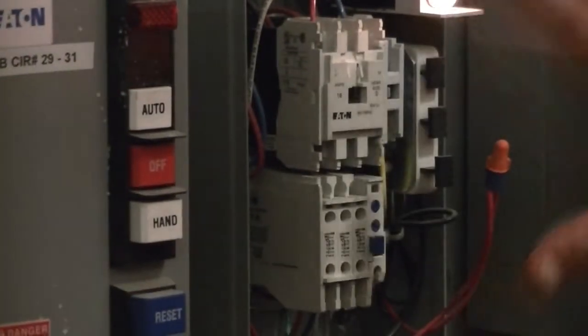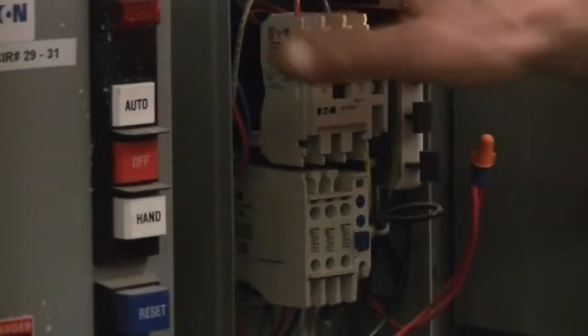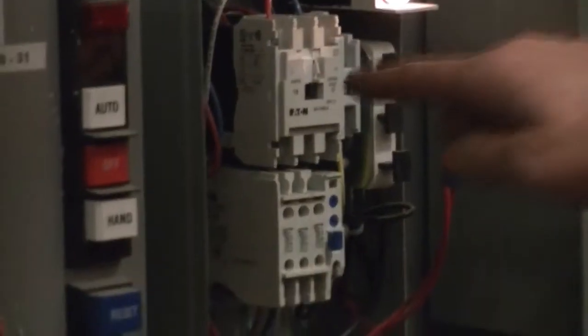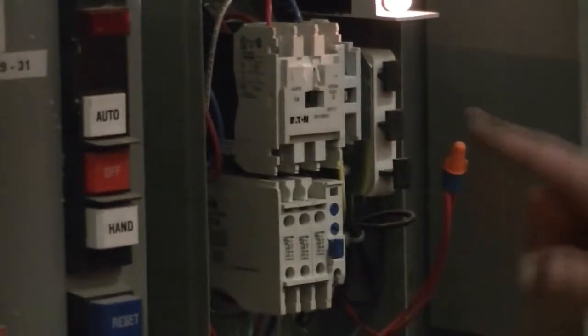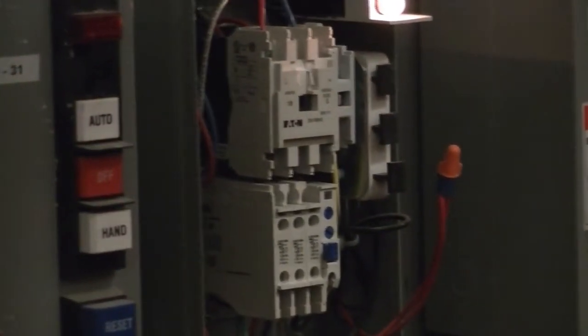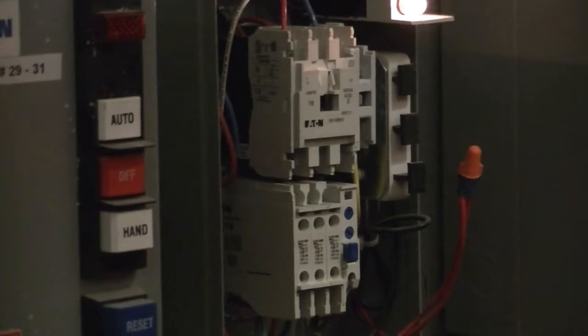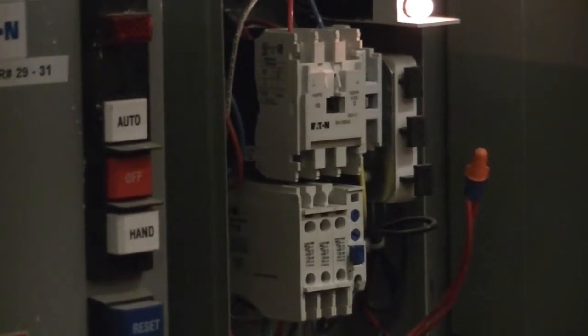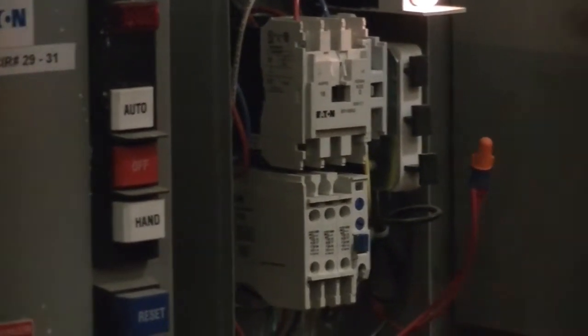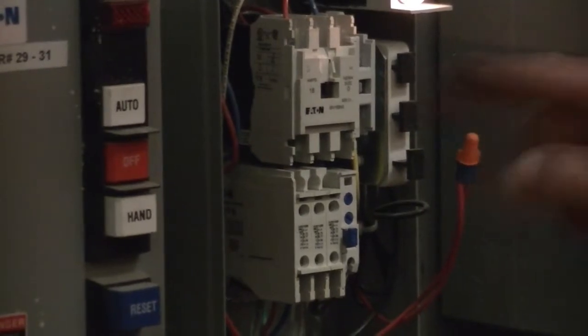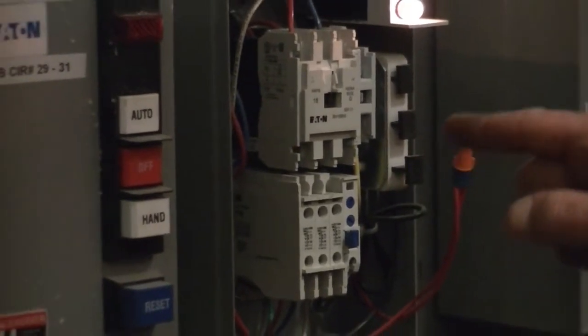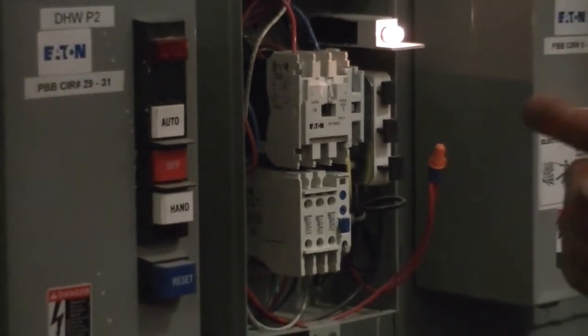There are 2 sources of power for this. One is power from the pump itself. The other is the signal power from the boiler. It's 110 volts from the boiler to engage the starter. Don't think that by turning the breaker off from the panel that you've killed this starter. You have to kill the boiler and you have to kill the pump power in order to work on this, okay? Because one thing tells the other to run.